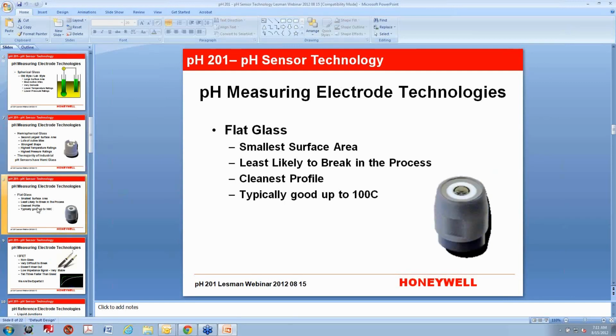The next one up is flat glass, and everyone in the industry was really happy to see flat glass come along, because if you have a process that is highly coating, or has a lot of particulates and it's moving swiftly through the pipe, it's easy for a hemisphere, and especially for a sphere, to get broken hanging out there in the process, even if you put some notches to protect it, etc. So flat glass is wonderful for those types of applications. Unfortunately, it has a smaller surface area, obviously, because now we're down to a disc instead of a hemisphere or a sphere. But it is the least likely to break in your process because it's not hanging out.